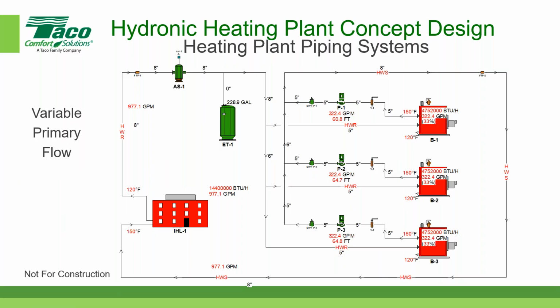My suggestion, again, since this diagram is not for construction, it's not meant to be an absolute representation of how you should do the piping, is to contact your boiler rep and have a discussion with them, for the type of boiler that you have, as to whether or not you want to pump into the boiler or away from the boiler. Generally speaking, you want to pump away from the boiler because the expansion tank, in this case, is on the suction side of the pump, but it flows through the boiler first before it gets to the expansion. I'm sorry, it flows through the expansion tank point of no pressure change connection before it gets to the boiler.